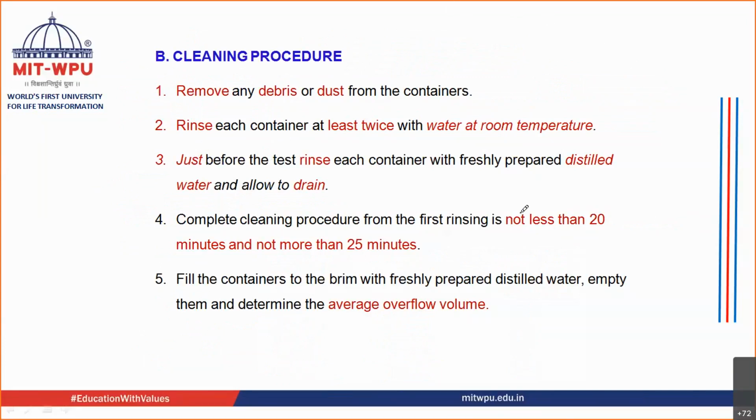How are you going to clean the containers that you have taken? First, if there is any debris or dust on the containers, you are going to remove that. Then you are going to rinse the container twice with water at room temperature. Then, just before the test is carried out, you are again going to rinse the container, this time with distilled water. Earlier you did it just with water, now with distilled water, and then you allow it to drain, so whatever surface impurities are there get removed from the container.